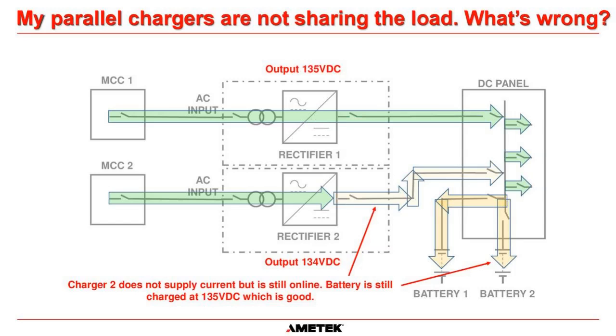And also, the feedback circuit in our charger has to monitor the output from its charger to be able to change its voltage. So what we do is we put a blocking diode here. Therefore, if rectifier 1 fails, yes, we get 135 volts at this point here. It goes back to this diode here. We get 135 volts there, but on the anode of this diode, you'll get 0 volts if this has failed. So we can sense within the charger that the charger has failed.